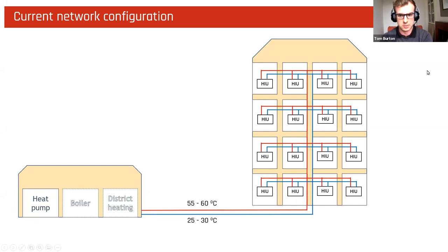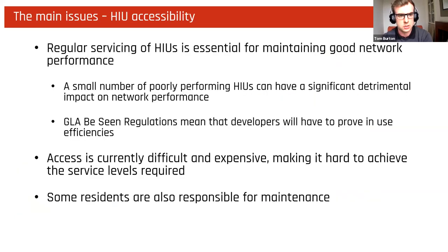But what I want to focus on here is the building side and the network routing options that you have. The first main issue, as the title might have given away, is accessibility of HIUs. This boils down to the fact that to maintain performance from handover throughout your network lifetime, you need to be regularly servicing HIUs. And this can't just be most HIUs, it really has to be 100%, because a very small number of poorly performing HIUs can have a significant impact on network performance.